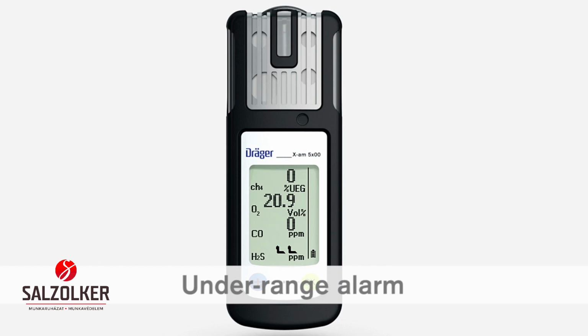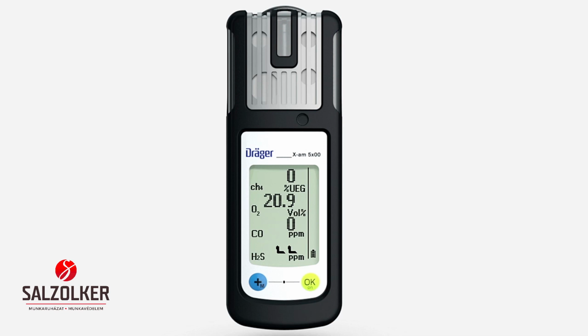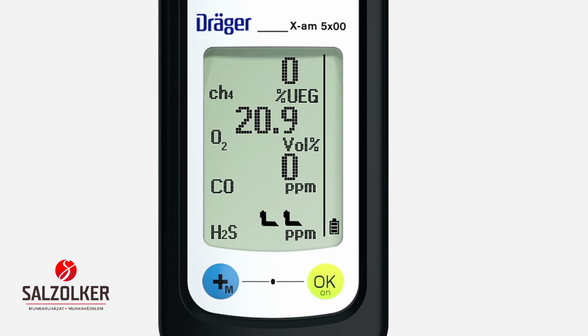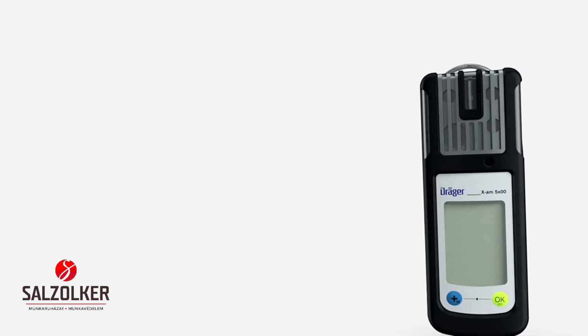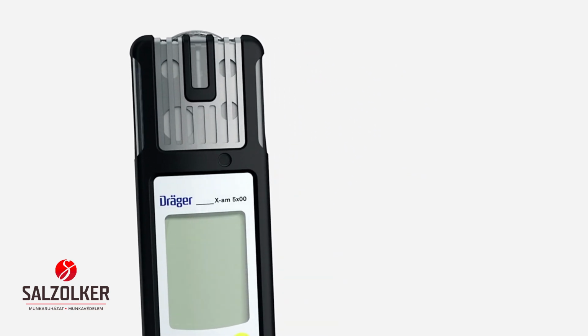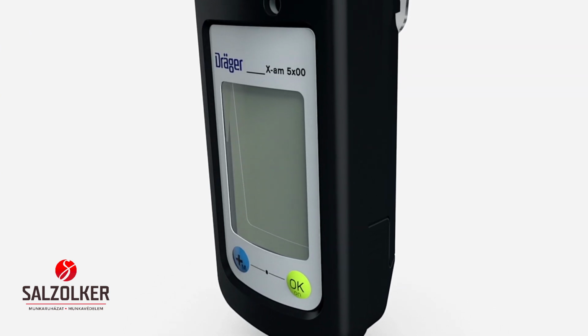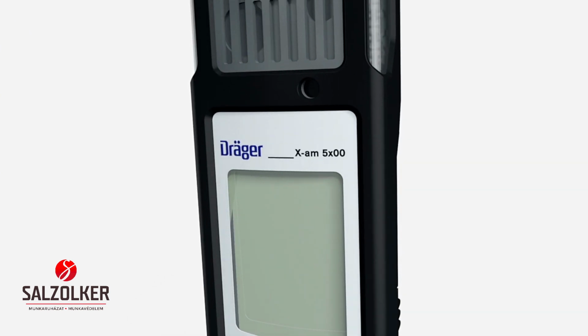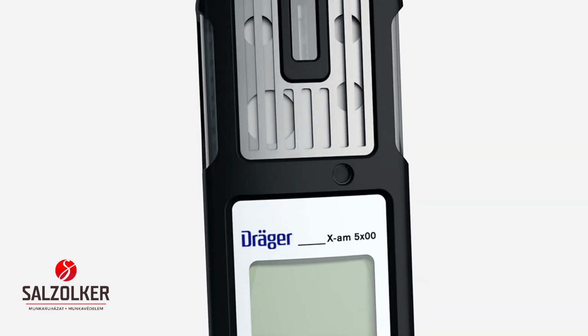In an underrange alarm in which the measuring range is not reached, the audible, visual and vibration alarms are repeated. The underrange symbol is shown in the respective measuring field. This indicates that the measured value is negative. This can occur if, for example, a fresh air calibration has been carried out in a range in which concentrations were already present. Perform fresh air calibration immediately in an area of fresh air. This alarm cannot be acknowledged.